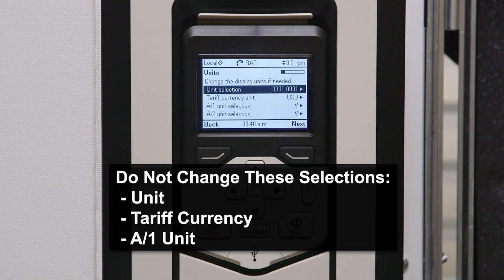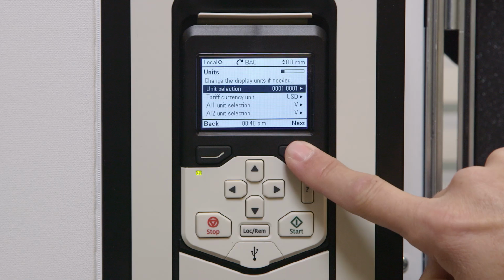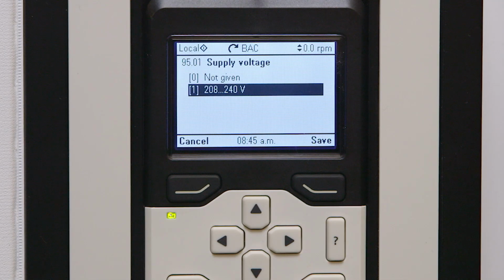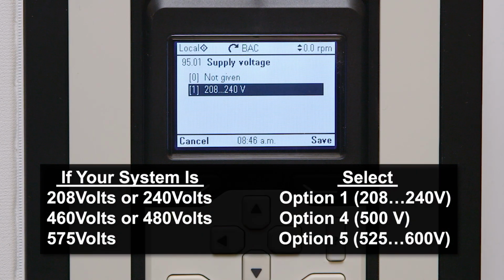Leave Unit Selection, Tariff Currency Unit, and AI1 unit selection at the default values. Press Next. Now the ACS880 will have us set up the supply voltage. If you have a 208 volts or 240 volts power system, select option 1, which displays 208 to 240 volts. For 460 volts or 480 volts power systems, select option 4, which displays 500 volts. If you have a 575 volts power system, select option 5, which displays 525 to 600 volts.